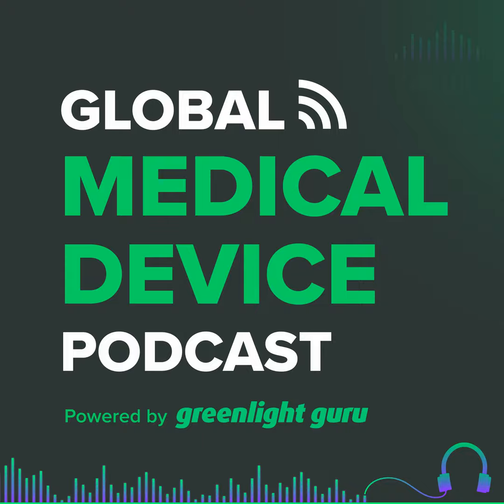If you're going to do a clinical trial for your NSR device and you don't tell FDA about it first, and again, you have no obligation to, and you spring it on them for the first time at the point of the submission, then be prepared for them coming back and saying, well, what about this other endpoint? You didn't measure this endpoint. We would like to see that. So now you may have to do a whole clinical trial over again in order to collect that information. Ka-ching, ka-ching, ka-ching. It's a calculated risk. Some companies might choose to take that risk. Other companies might not.